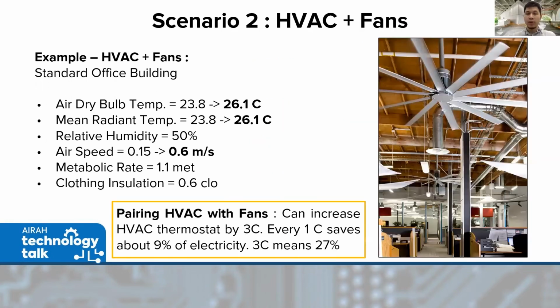Now what if we add fans to it? As I said, adding fans increases convection cooling, so we can increase the HVAC thermostat set point. Let's increase that set point from 23 degrees to 26.1 degrees. Because we have elevated airspeed due to the fans moving, airspeed increases from 0.15 to 0.6 meters per second. Same building, same parameters, except the air temperature and airspeed. What do we get?